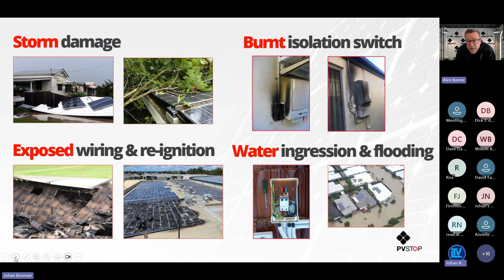Firefighter injuries directly related to solar panels have been recorded in Switzerland, the UK, and the US. Now there's an issue with reporting systems. A lot of injuries that may be a direct consequence of PV systems can instead be recorded as working-from-height issues or small electrical events, which trigger another series of events leading to injury. The PV system's involvement tends to be overlooked, since most reporting systems don't have the capacity to say the PV system was a direct cause or root cause of the injury.